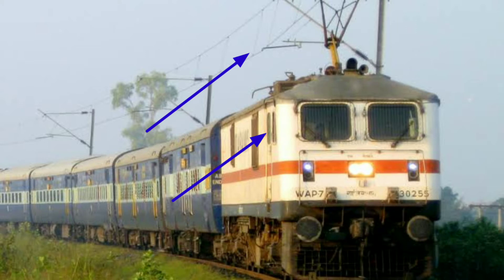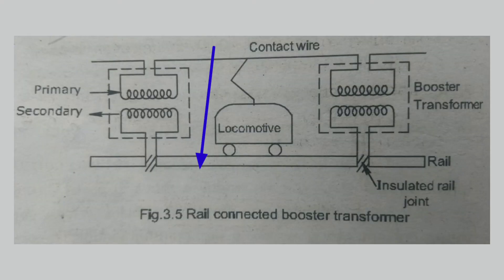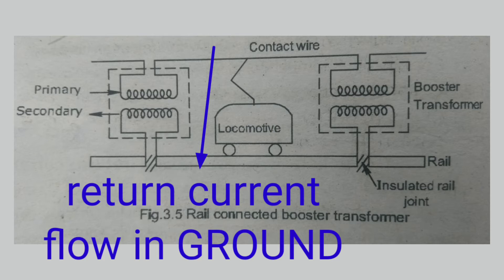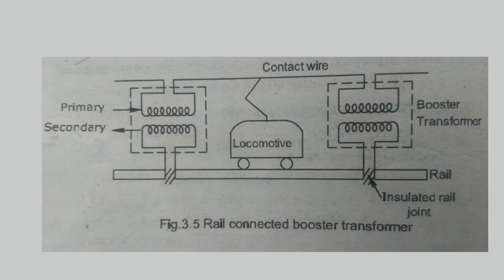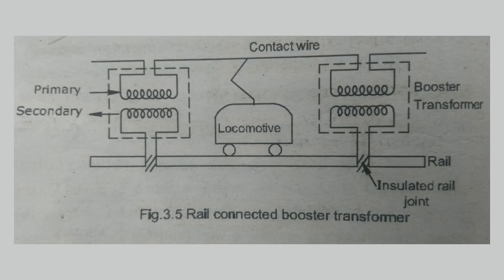In the Booster Transformers, we use an AC Traction System with a railway electric train. In the AC Traction System, the return current goes to ground. If it reaches the ground, the communications line will be affected — for example, a TV, a radio, or a telephone call will experience interference. This is a communication effect in the AC Traction System.